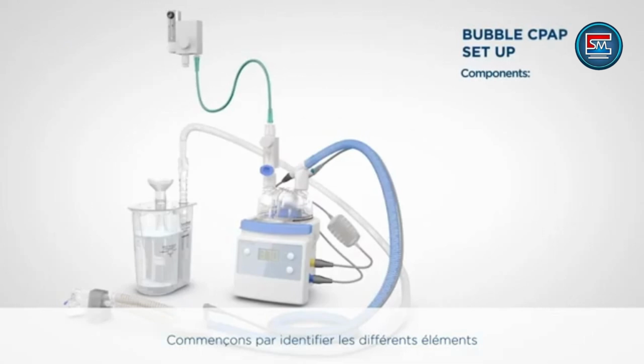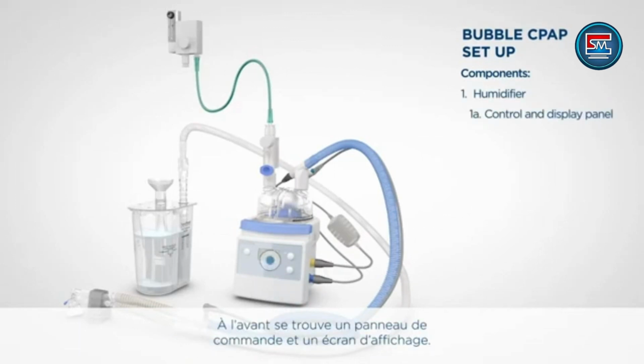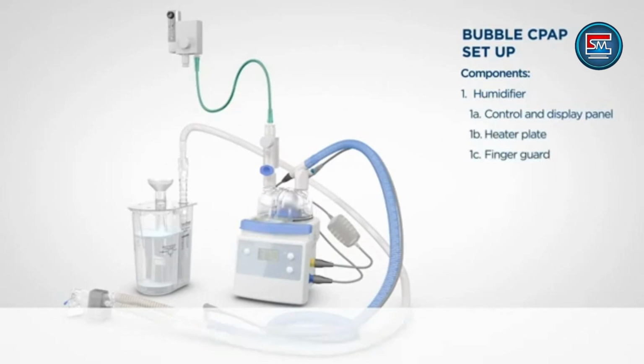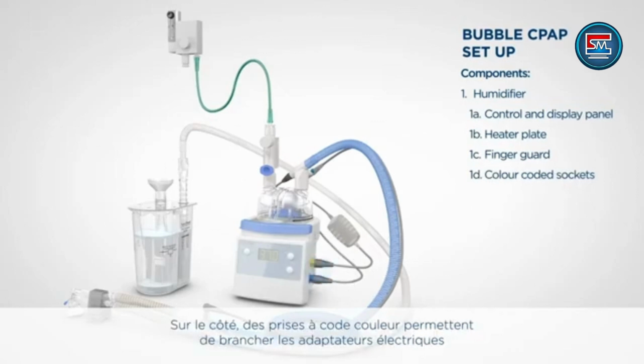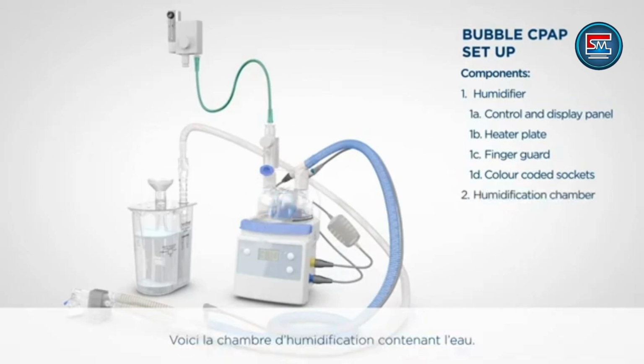Let's start by identifying the components of the F&P Bubble CPAP delivery system. This is the humidifier. It has a control and display panel at the front, a heater plate and finger guard on top, and color-coded sockets to connect electrical adapters and sensing probes on the side. This is the humidification chamber that holds water. It is filled from a rigid or flexible water bag through the water feed tube. This is the pressure manifold. It is designed to limit the pressure to 17 centimeters of water at 8 liters per minute.